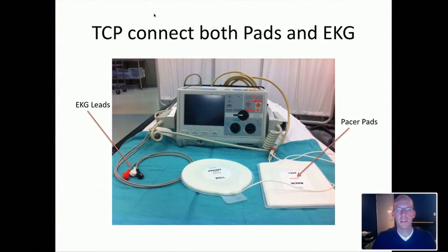So let's look at this. This is the pacemaker that we have here at Stanford. It's part of the defibrillator. Important to note that you need to hook up both the EKG leads with the defibrillator pacemaker and the pads. And the reason for that is that the pacer pads can either send or receive energy, but it can't do both, meaning that it can send out electrical energy to pace, but that means you can't interpret the rhythm. Therefore, if you're using the defibrillator as your monitor, you're not going to see if you're getting capture.